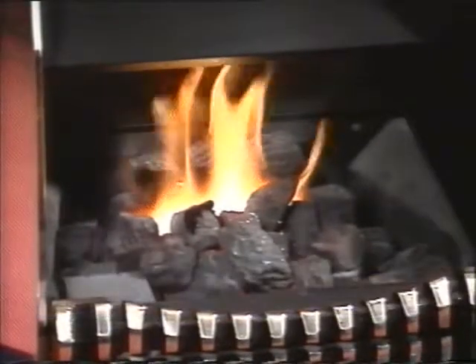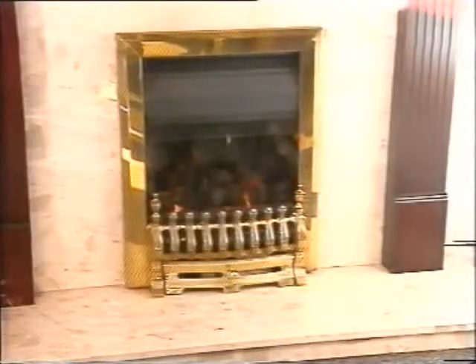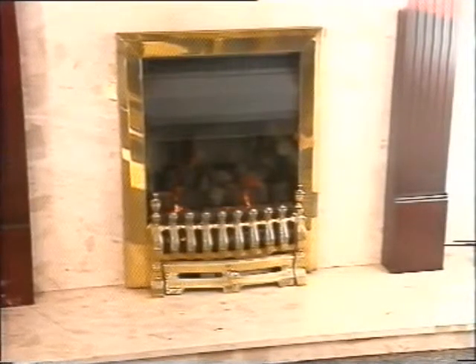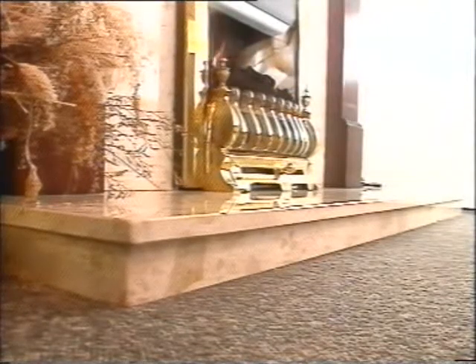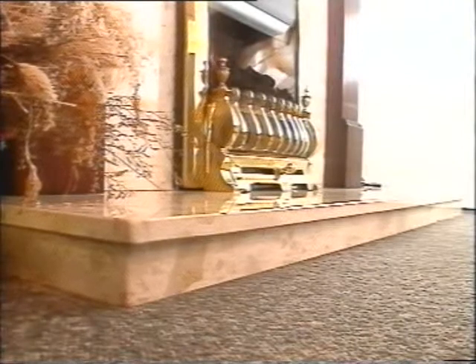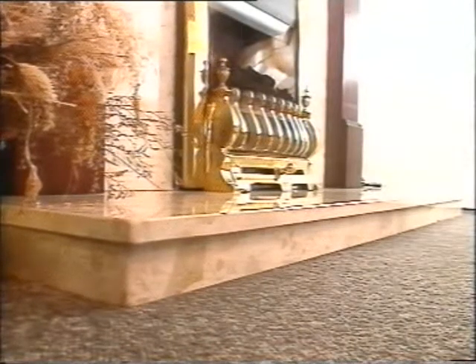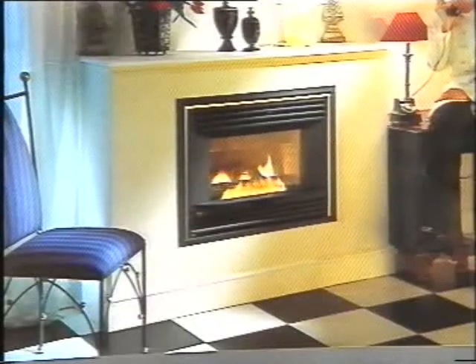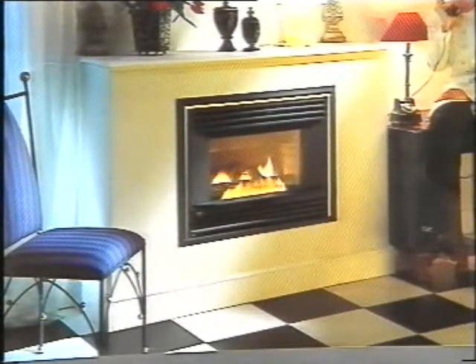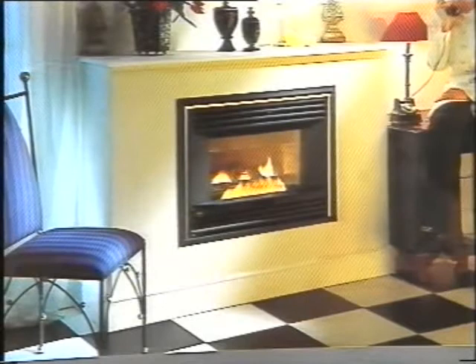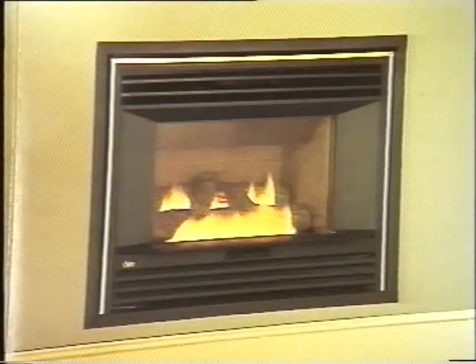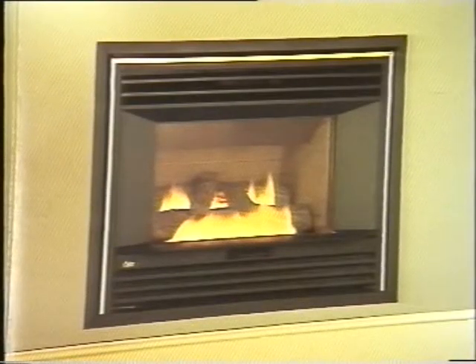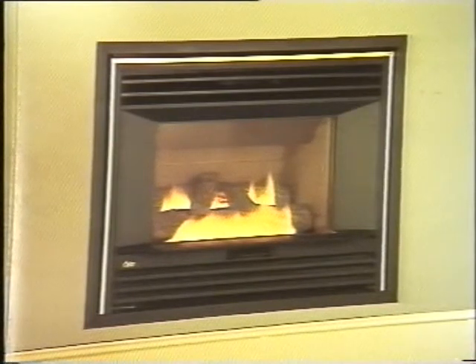With ILFEs, the top surface of the hearth has to be at least 50 millimeters above floor level. An upstanding edge, like a fender along the front and sides, would do as long as it's 50 millimeters high. The idea is to discourage folk from putting carpets or rugs on top of the hearth. Wall-mounted ILFEs don't need a hearth if the flame or incandescent material is at least 300 millimeters above the floor. Some manufacturers, though, may ask for a hearth to be fitted in case hot coals fall out of the fire.